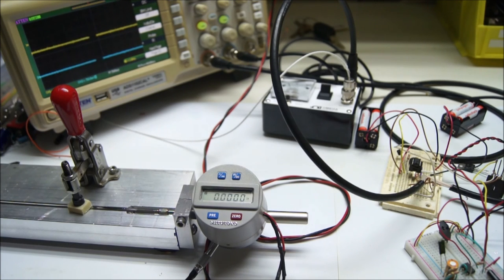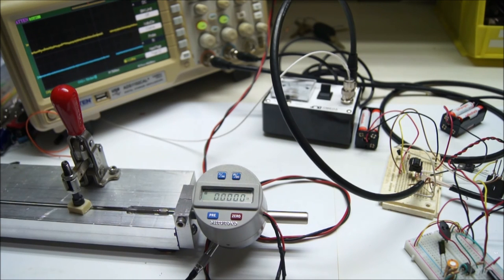Now, put it in the forward position, or forward mode, and we'll advance the drive tube until the clip is at the forward deployment position. And we'll see that in the indicator there. It's going to be about 40 thousandths.